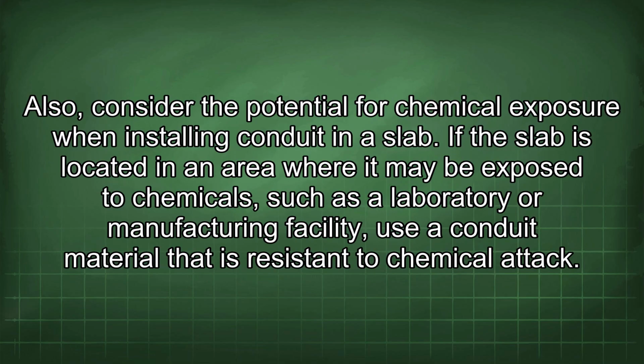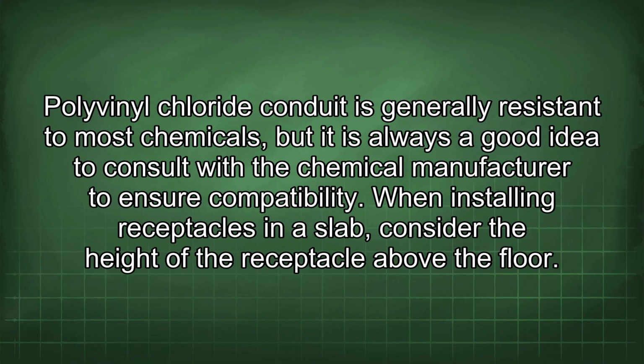Also, consider the potential for chemical exposure when installing conduit in a slab. If the slab is located in an area where it may be exposed to chemicals, such as a laboratory or manufacturing facility, use a conduit material that is resistant to chemical attack. Polyvinyl chloride conduit is generally resistant to most chemicals, but it is always a good idea to consult with the chemical manufacturer to ensure compatibility.